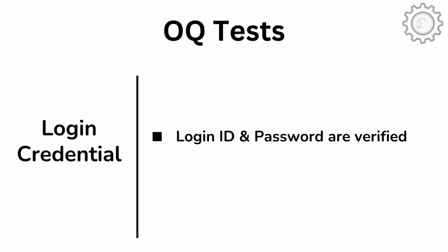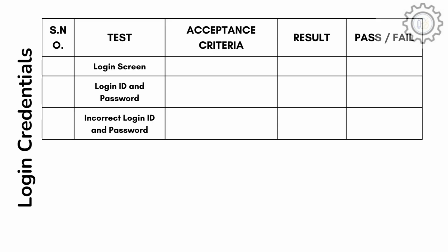Login credentials. In this test, login is verified according to the requirements. It includes whether the manufacturer has supplied all the required levels of password protection as agreed during the design qualification stage. Some tests that are common include whether login screen is available, whether the system accepts the correct login ID and password. Similarly, whether the system rejects the wrong login ID and password.